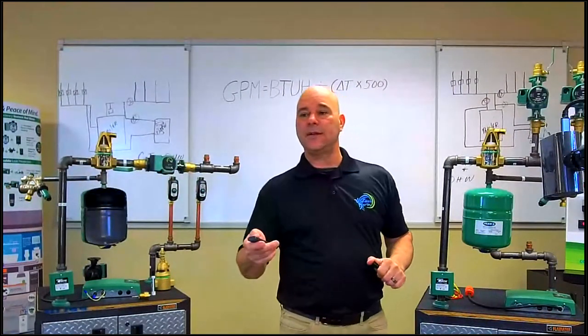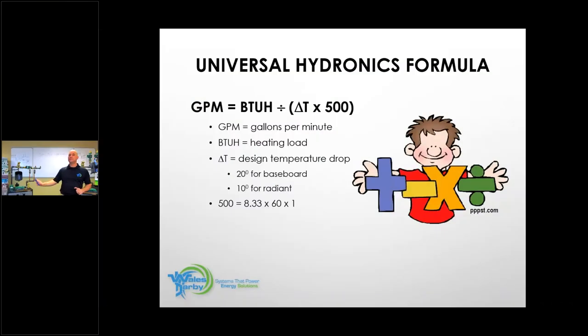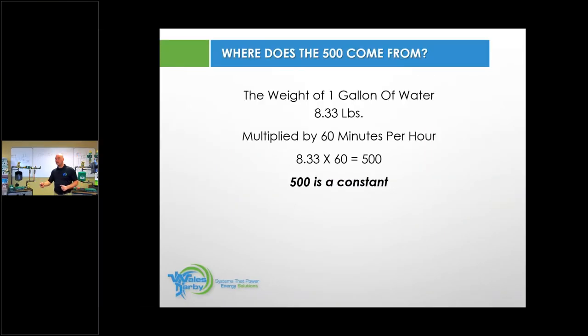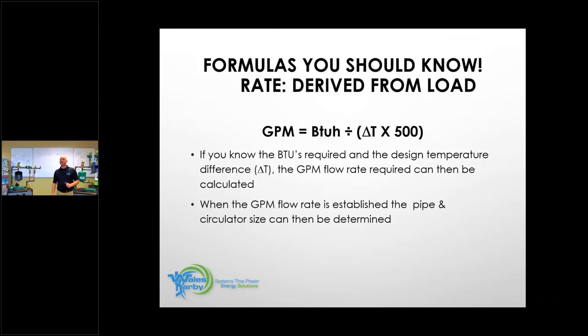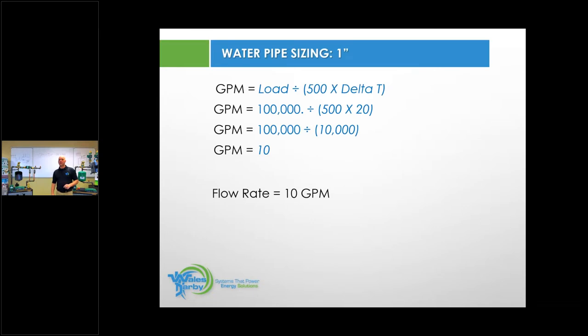So what does this look like? There's the gallon of water, 8.33 pounds. Multiply that by your hour. There you go, 500. That'll be consistent. So knowing this formula is going to be huge. We broke it down one more time here. Gallons per minute equals load divided by 500 times delta T. So here we're giving you a 20 degree delta T.